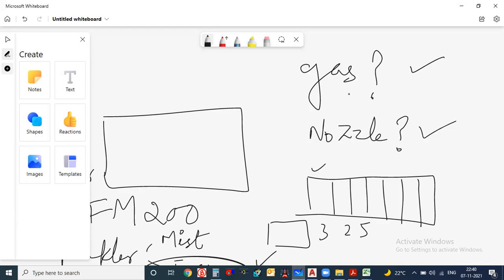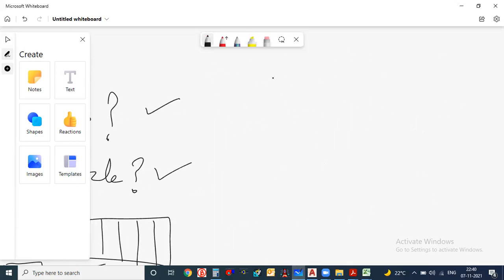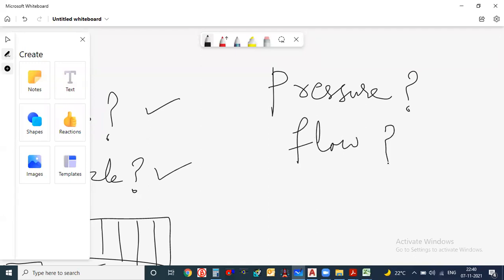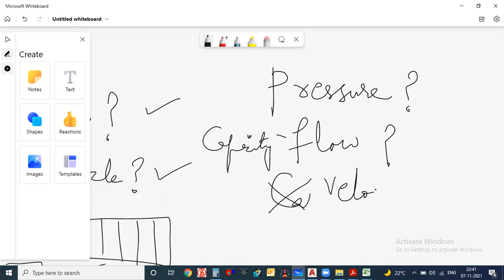As a design engineer, this is what I understood from firefighting: we need to know only two or three things, like what is the pressure I'm going to maintain in this building, what is the flow I require in the building, and sometimes if going with gas, what is the capacity. Capacity tells everything, like the flow and the pressure. And since you are doing the allied calculation, you can also calculate the maximum velocity. So a design engineer is restricted to only these three things.